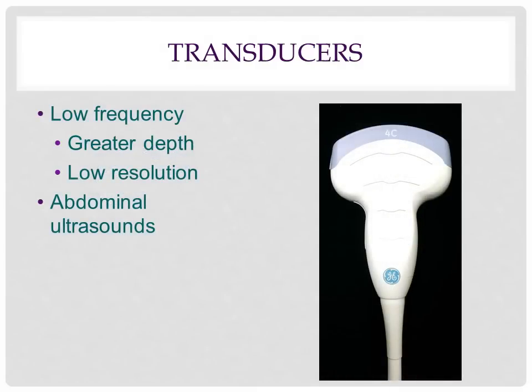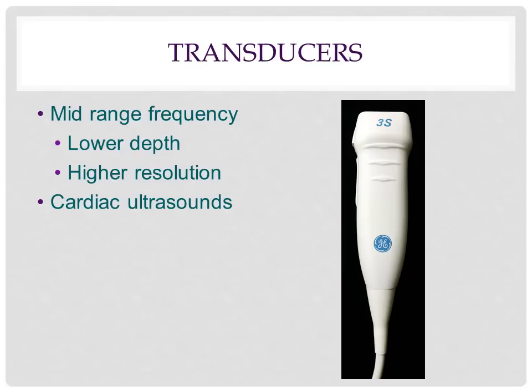A low frequency probe, such as the 4C curvilinear probe, will be used during abdominal ultrasound scans. It has a low frequency, which allows for greater depth but a lower resolution. It also has a wide footprint, allowing it to scan larger areas of the abdomen. In contrast, the 3S transducer probe has a higher frequency range. This produces higher resolution images, but means sound waves do not travel deep into the body. With a small footprint, the probe can send sound waves between ribs, making it the optimal probe for cardiac ultrasounds.